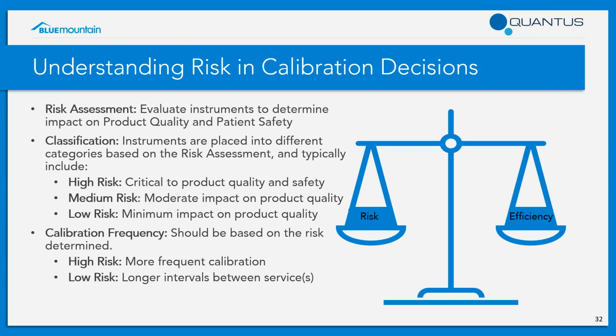Classifications of instruments are typically defined into a couple of different risk categories that I have on the screen here. High risk instruments are critical to your product quality and patient safety, and any errors in those instruments can lead to significant health risk or regulatory non-compliance. Medium risk instruments have more of a moderate impact on product quality and safety, and errors may result in quality deviations, but may not be an immediate health risk. And your lower risk items are things that have no impact to patient or product safety, like in your R&D lab. Also, in your risk assessment, this is where you can help identify your calibration frequency. Higher risk instruments may require service more often, while a lower risk instrument can have a longer interval between services.